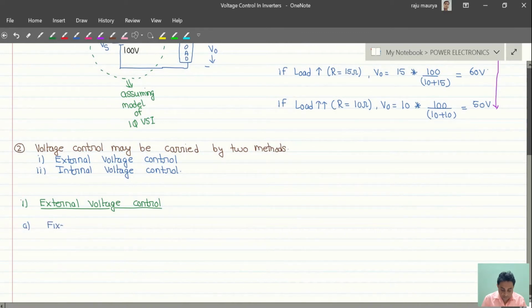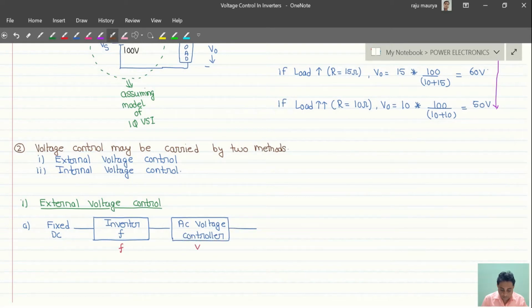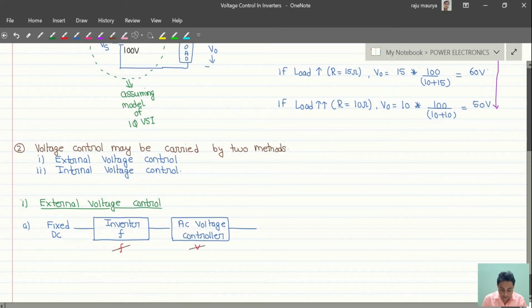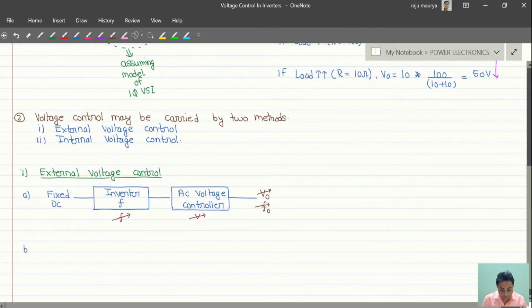In external voltage control, a fixed DC is first fed into an inverter and then fed to an AC voltage controller. In the inverter we vary our frequency, and in the AC voltage controller we vary our output voltage. So at the end we get variable voltage and variable frequency.